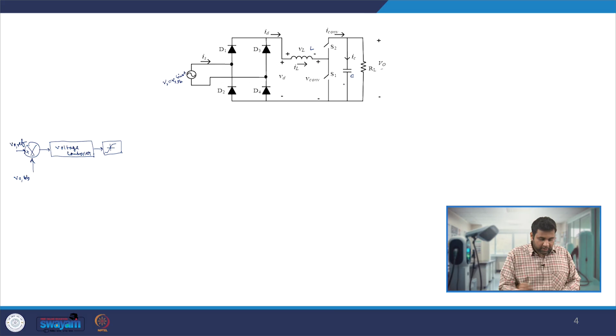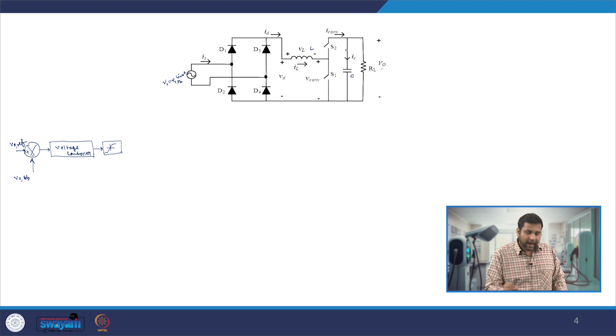Now, let us understand why we need this saturation block. In this particular arrangement, we have the reference voltage which we need to maintain at the output, and we are also comparing it with the feedback. If there is a difference, for example, if the reference is kept at 400 and the feedback is at 350 volt, then it indicates that the capacitor needs to be charged up. So the current drawn by the capacitor needs to be increased such that the capacitor voltage will rise and reach the V naught reference value.